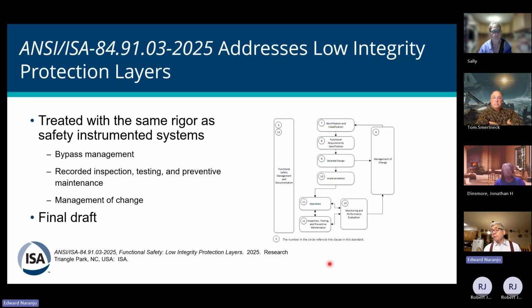However, their approach to the problem is that they just need to make small increments of risk reduction to get to the level that they want. They're not considering that they need to review the process entirely to come up with one, perhaps two steps that are going to help them achieve their SIL target. Okay?